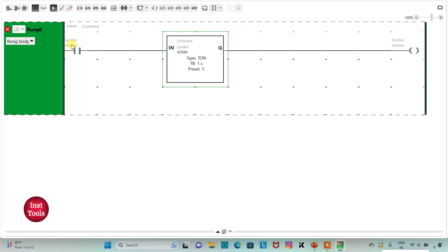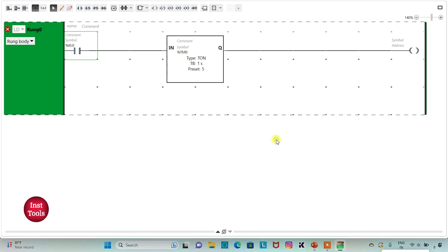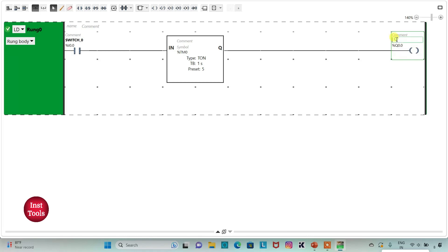Then I will assign an address to this contact as I 0.0. I will also add a symbol to it as switch 0. And then I will assign an address to this coil as Q 0.0 and symbol as output 0. So when I turn on switch 0, after 5 seconds the output 0 will be on.